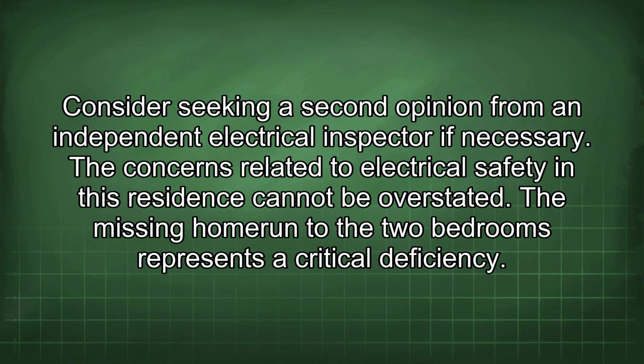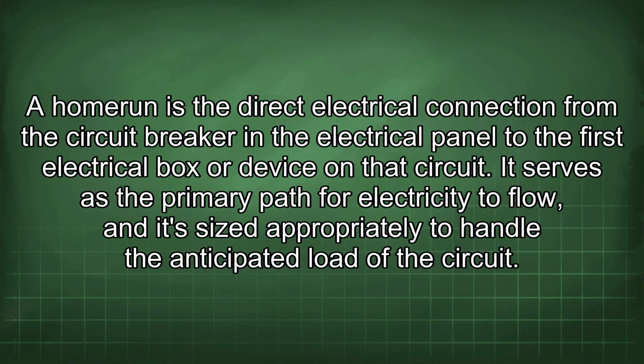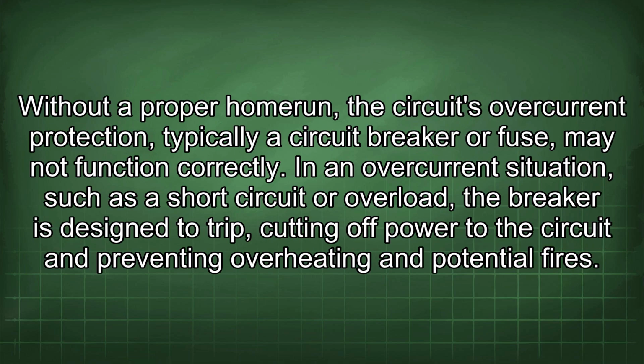The concerns related to electrical safety in this residence cannot be overstated. The missing home run to the 2 bedrooms represents a critical deficiency. A home run is the direct electrical connection from the circuit breaker in the electrical panel to the first electrical box or device on that circuit. It serves as the primary path for electricity to flow, and it's sized appropriately to handle the anticipated load of the circuit. Without a proper home run, the circuit's overcurrent protection, typically a circuit breaker or fuse, may not function correctly. In an overcurrent situation, such as a short circuit or overload, the breaker is designed to trip, cutting off power to the circuit and preventing overheating and potential fires.